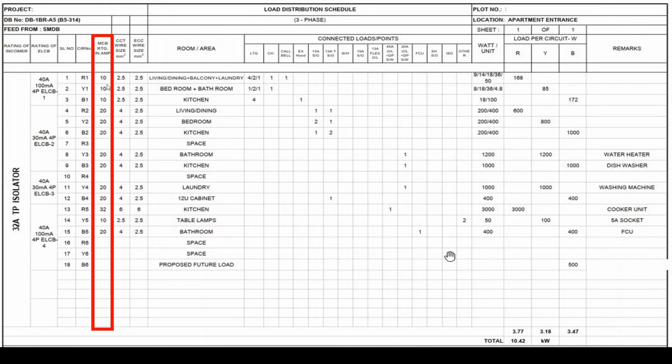The lighting section, you would usually connect a maximum of 1200 watts. In the earlier days, we were assuming 100 watts for each light point, so you would connect a maximum of 12 points for each lighting circuit. But currently, technology has developed, and since we have green regulations in place and we are trying to implement environmentally friendly practices, most lights nowadays are LED, which is rated at 10 watts, 12 watts, 15 watts, 20 watts. So you typically connect many more than 12 points, and the final load will not reach 1200 watts.